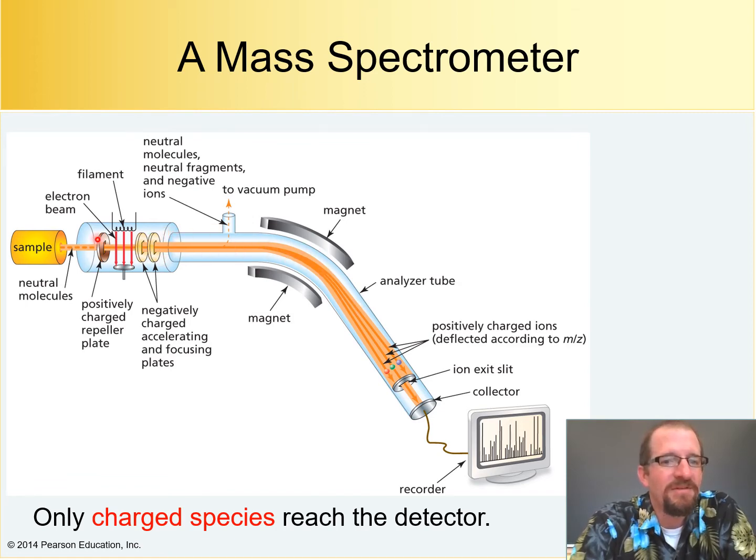And what happens is this thing shoots the molecule, and as it goes here, if it wasn't for this magnet, it would just ping into the side of the tube. But instead, there's this magnet here that applies a magnetic force to it, so that it's attracted to that magnet. And therefore, as it goes, the heavier molecules feel that magnetic force less and are over on this side of the beam.